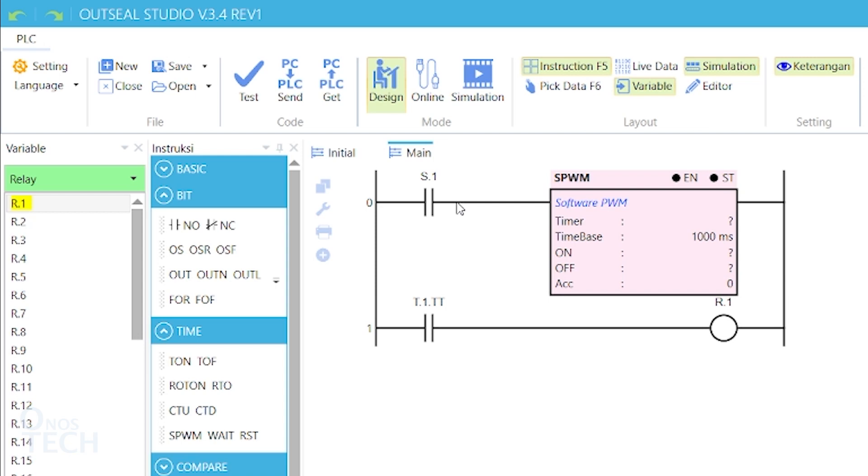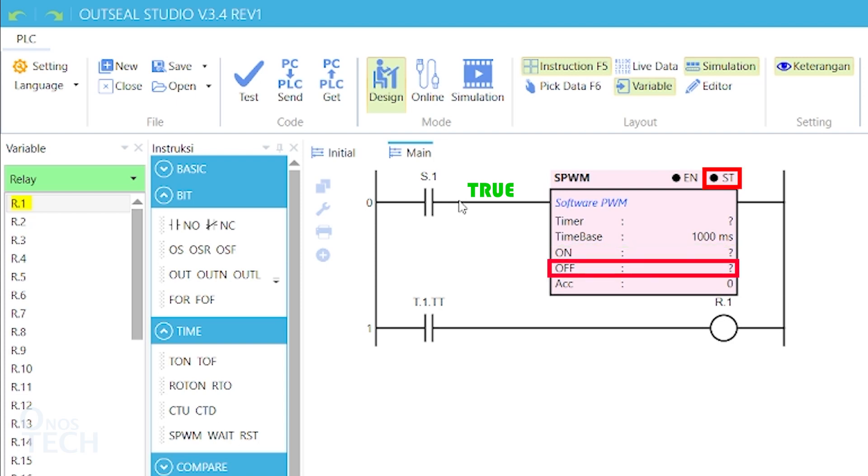When the rung condition is true, ST will be true for the duration of the ON value multiplied by the time base. Then, it will become false for the duration of the OFF value.